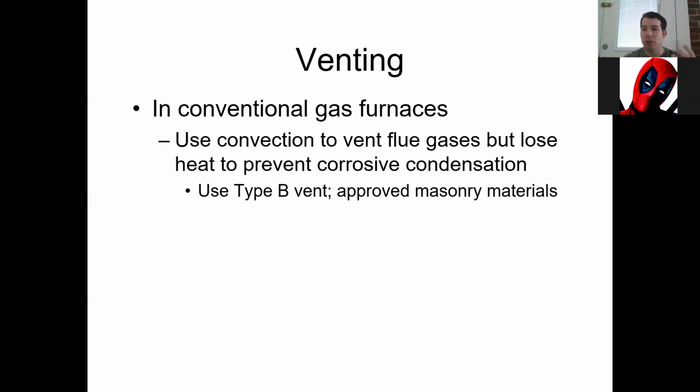When you had an older, less efficient furnace, less efficiency means that your flue temperature is going to be higher. You're going to have really, really high flue gas temperatures from a low efficiency furnace, while you'll have very low temperature flue gases coming from a high efficiency furnace. Because with the high efficiency, we're holding on to more of that heat. We've got more things to do with that gas now that we're holding on to more of its heat, but we'll get into that.